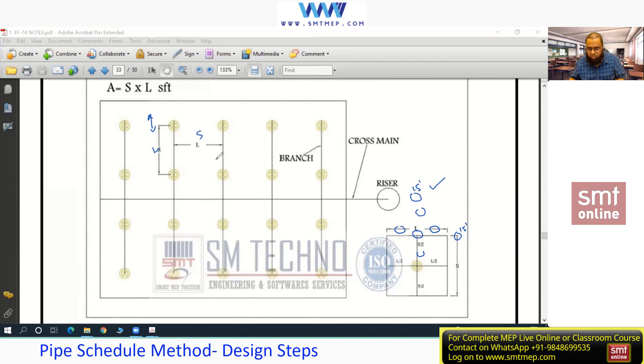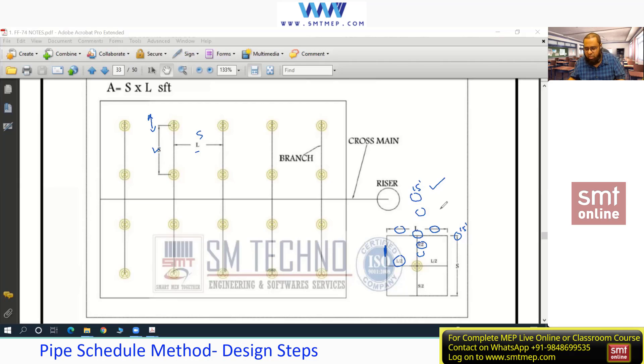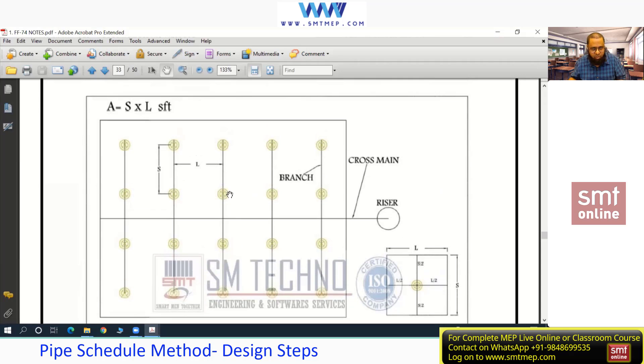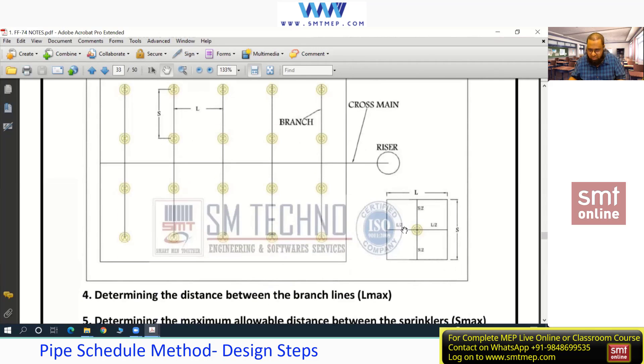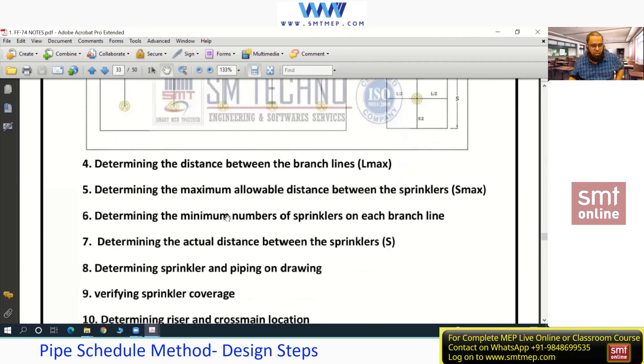For example, if the distance between sprinklers is 3 meters — most common in actual practice for small or medium projects — the distance from the wall is 1.5 meters, which is L/2 or S/2. This will vary based on hazard. The formula A = S × L is important and will be used in calculation. One side of a sprinkler covers S/2 or L/2 — remember this for calculation.